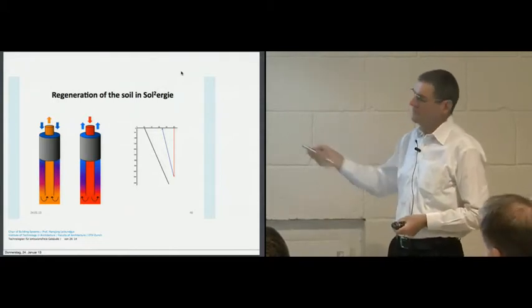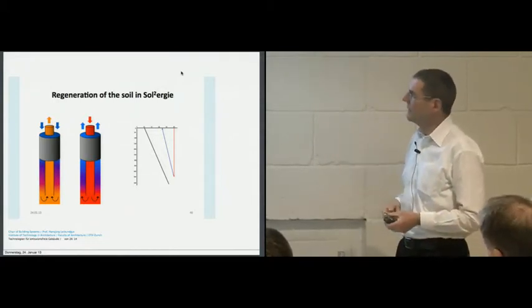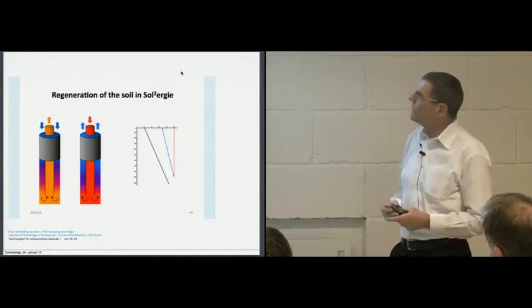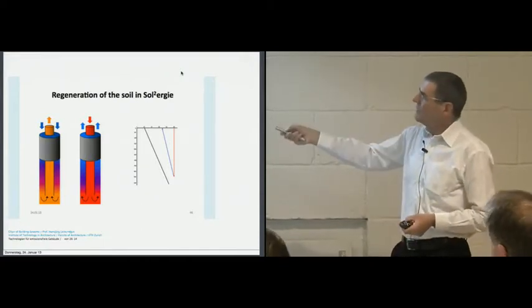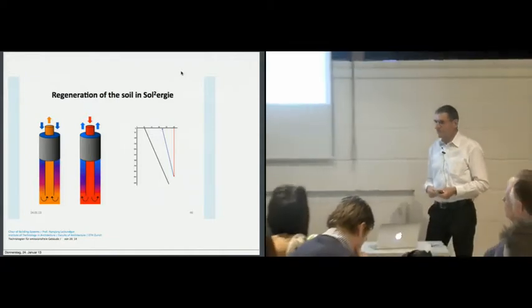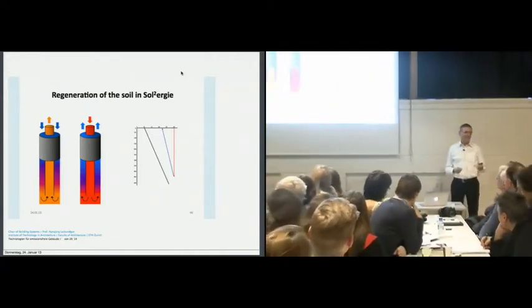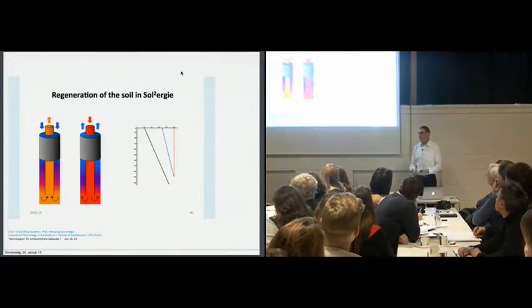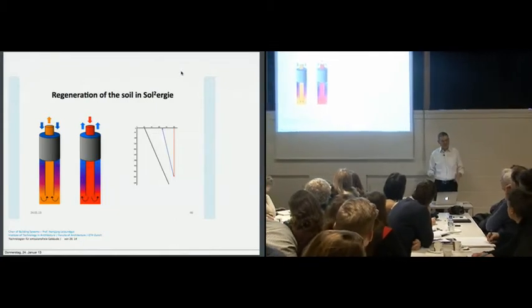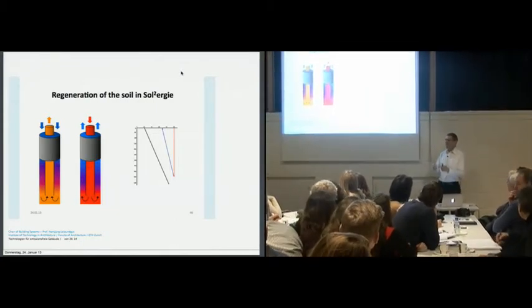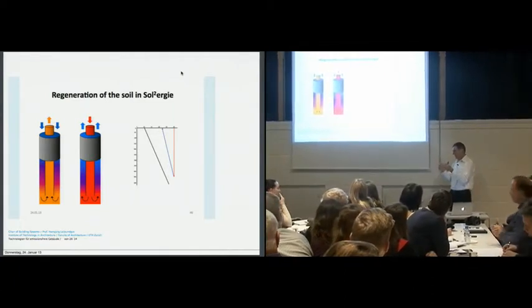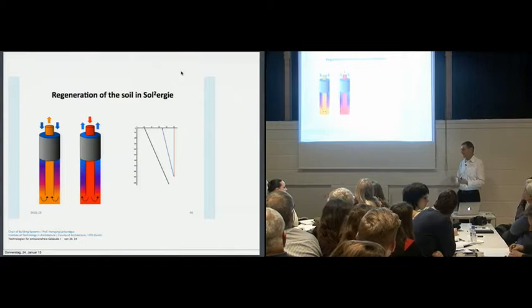What we do now, and this is a patent we wrote about four months ago: we drill a hole of 450 to 500 meters with a diameter of about 14 centimeters. Normally, if you insert U-tubes, earth probes, you have to fill the space between the tubes and the rock with concrete, in order to give good thermal contact.